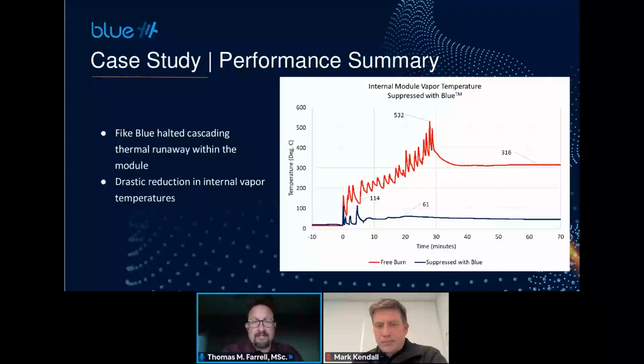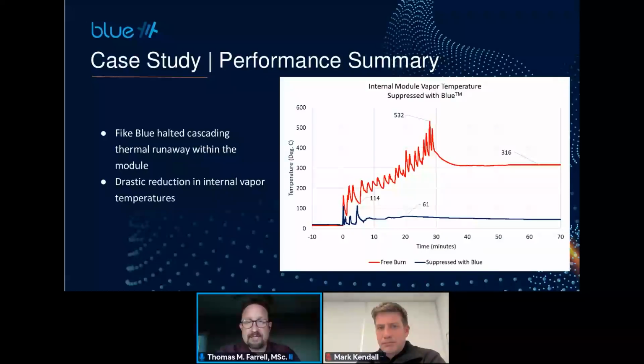Now you can imagine if that is very close to another module, that would cause significant heating if you had that jet impinging on another ESS module in that same space. And then once those gases were exhausted, it led to a plateau of about 316 degrees, which lasted at that level for several hours before eventually starting to cool. And like I said, about 24 hours later, it was still just above 100 degrees Celsius.